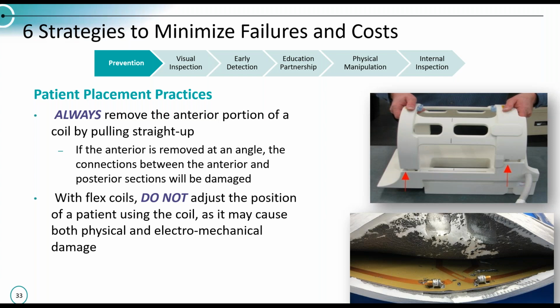With flex coils, we don't want to adjust the position of the patient while they're laying on the coil. There's a shot of some of the components embedded in that flex circuitry, and those things can become torn, the solder connections break, and then you end up with intermittent problems or a hard failure.